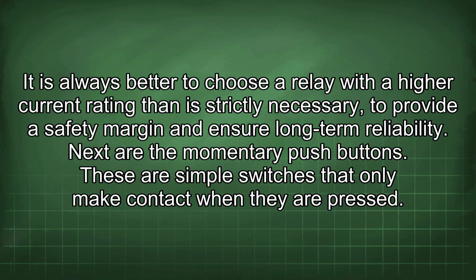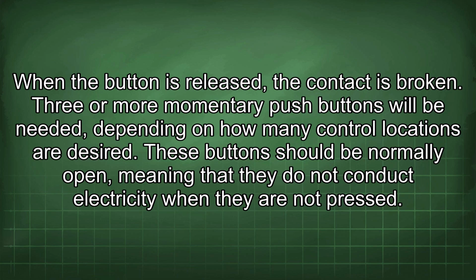Next are the momentary push buttons. These are simple switches that only make contact when they are pressed. When the button is released, the contact is broken. Three or more momentary push buttons will be needed depending on how many control locations are desired. These buttons should be normally open, meaning that they do not conduct electricity when they are not pressed.